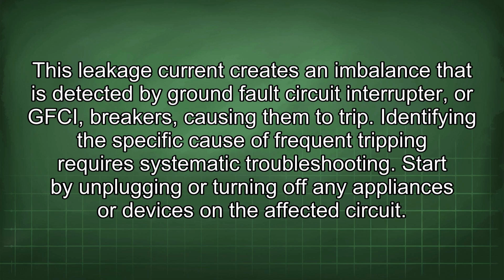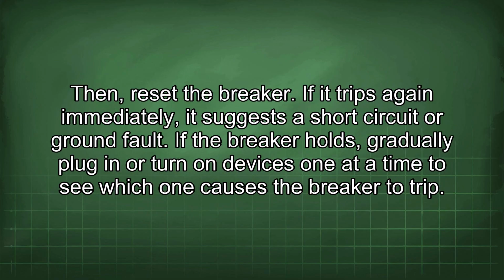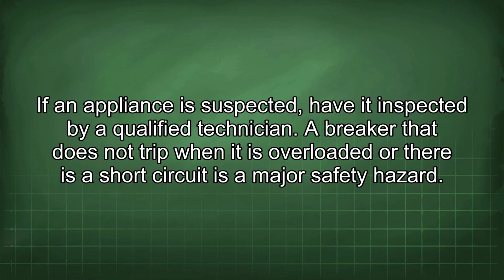Start by unplugging or turning off any appliances or devices on the affected circuit. Then reset the breaker. If it trips again immediately, it suggests a short circuit or ground fault. If the breaker holds, gradually plug in or turn on devices one at a time to see which one causes the breaker to trip. If an appliance is suspected, have it inspected by a qualified technician.